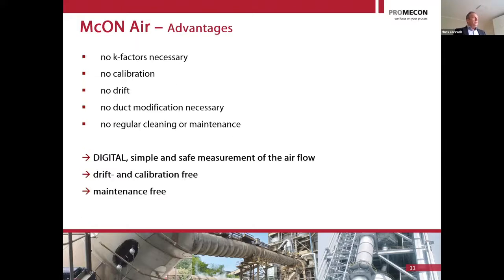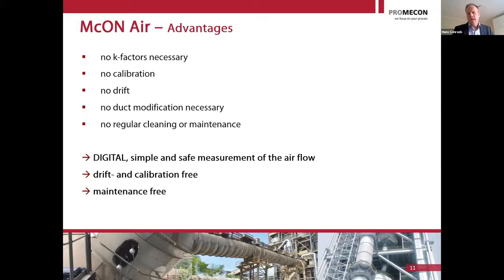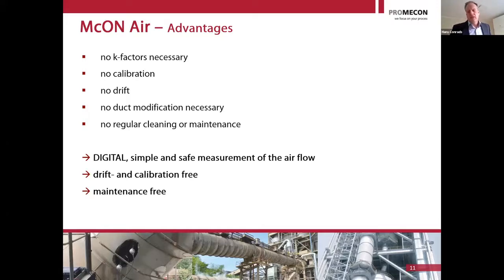The main advantages are: no K-factors, no calibration, no drift, and no major duct modifications necessary. You have two mounting lugs, you put the sensors in, and that is your measurement. You don't need to install any orifice plate or make any big modifications to the duct, and there is no regular cleaning required.